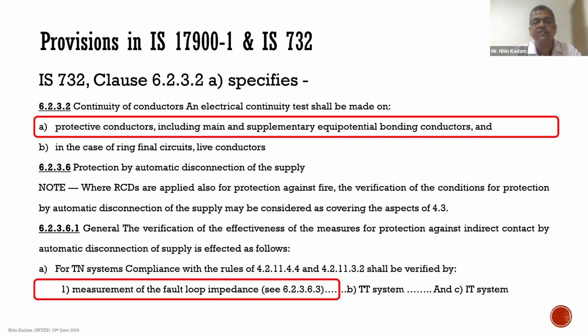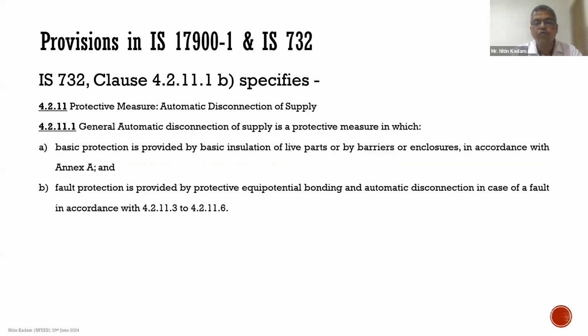It also further states that the protective conductors, including the main and the supplementary equipotential bonding, have to be checked. And for the TN systems, the measurement of fault loop impedance has to be done. Now, further, clause 4.2.11.1b specifies the fault protection by protective equipotential bonding and automatic disconnection of the power supply in case of faults, according to clauses 4.2.11.3 and 4.2.11.6. We'll see what these are in detail in the subsequent slides.